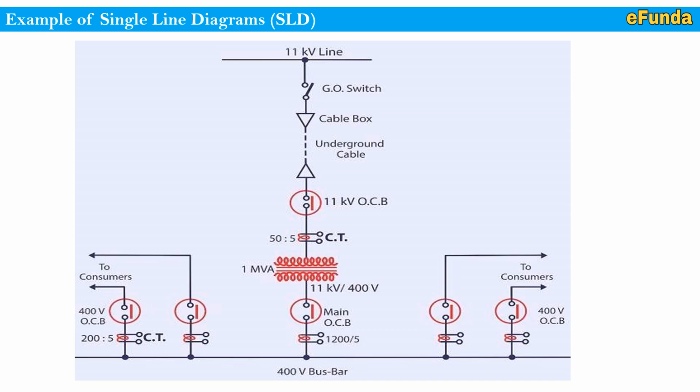A single phase residential load can be connected between any of these phases and the neutral. Then the three phase 400 volt motor load is connected across the three phase line directly. Then the current transformers are located suitably in the substation and supply for the purpose of metering and indication. Then the secondary of the main transformer is supplied to the bus bar through the main circuit breaker.